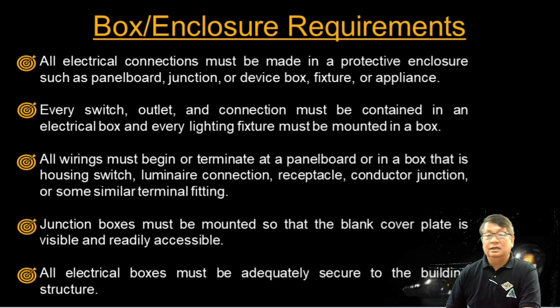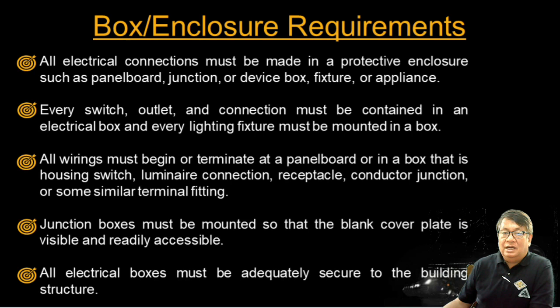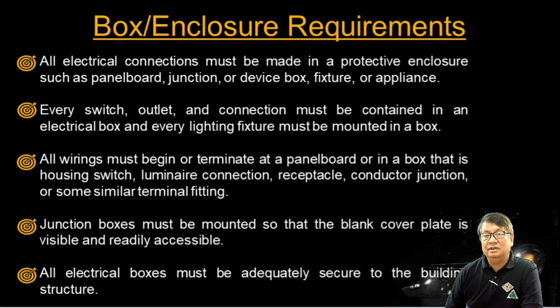So, box or enclosure requirements. Electrical connections must be in a protective enclosure, such as a panel board, junction, device box, or fixture or appliance. Any switch, outlet, and connection must be contained in an electrical box, and every lighting fixture must be mounted in a box. A junction box must be mounted so that the blank cover plate is visible and readily accessible.